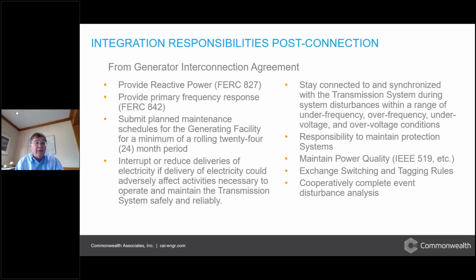You have to stay connected during a disturbance, so that goes back to our PRC 24. You have a responsibility to maintain your protection systems. You need to maintain power quality. So, that harmonic study, you can say, all right, it's met, but there's a mutual agreement between the transmission owner and the generator to maintain that. You have to obey switching and tagging rules, and you have to cooperatively complete any disturbance analysis.